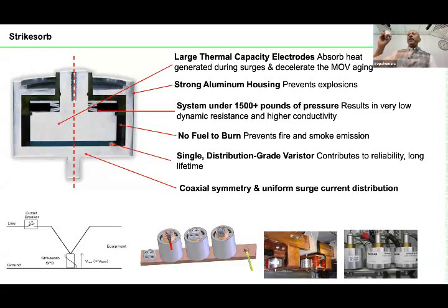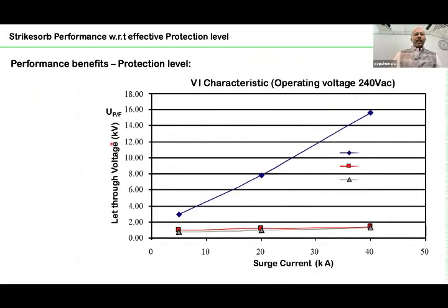For example, this SPD is tested for 10 kiloampere, 1000 strikes. You can imagine how many lightning strikes it can handle. Whereas the other one, DIN rail mounted, can handle only, for example, 20 strikes. The 21st, it may fail. Now, the advantage of this particular SPD is, before going to the advantage, I will show you the background of this discussion. Then I will come back to this particular slide.